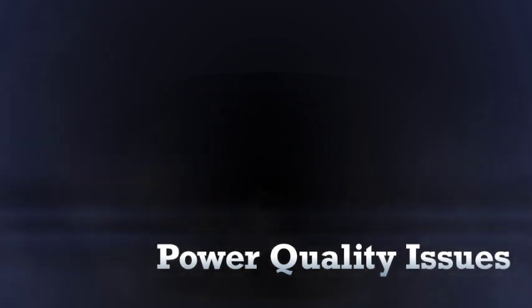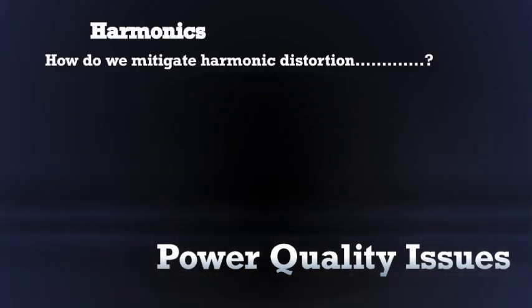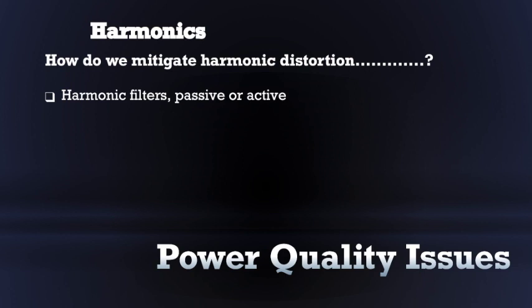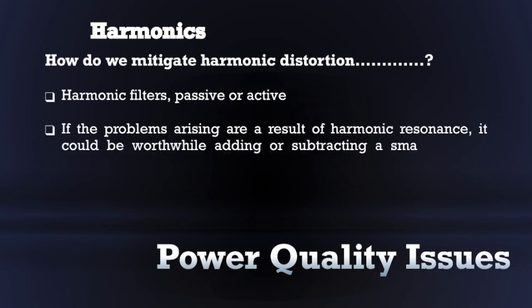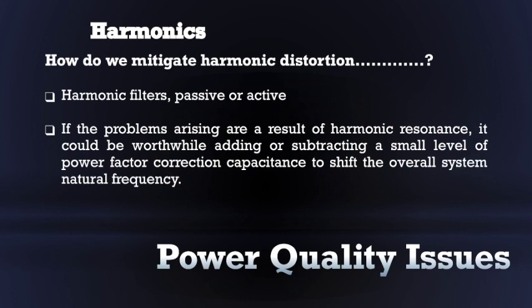Now the most important question, how do we mitigate harmonic distortion? We can go for harmonic filters, passive or active, which can be added to the system to suppress harmonic frequencies. Passive filters are tuned to filter a specific frequency or group of frequencies. Active filters measure the harmonic currents present in the system and generate opposite harmonics to cancel those produced by the harmonic sources. If the problem arising is a result of harmonic resonance, it could be worthwhile adding or subtracting a small level of power factor correction capacitance to shift the overall system natural frequency.